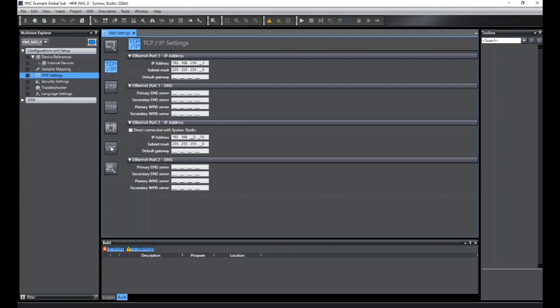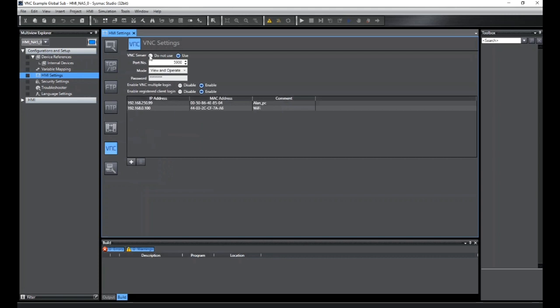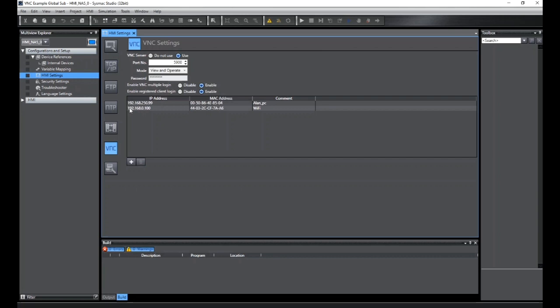Staying in this section, go to VNC. Here I have some button tabs. Enable the VNC server. Use defaults to port 5900. Mode, we have a choice of view only or view and operate. Password, we've got here 1, 2, 3, 4, 5, 6, 7, 8. Underneath here we have tabs to disable or enable multiple viewers and tabs to enable and disable a white list, i.e. what IP addresses are allowed to communicate to the NA. I currently have that enabled. I've put in my PC address on ethernet here and my PC address through the router on wi-fi here. I also tie up with the MAC address to give it a unique connection and any comments we wish to fill in here. These fields can then be read by the HMI if you wish. To add any more on the white list, just press the plus key.